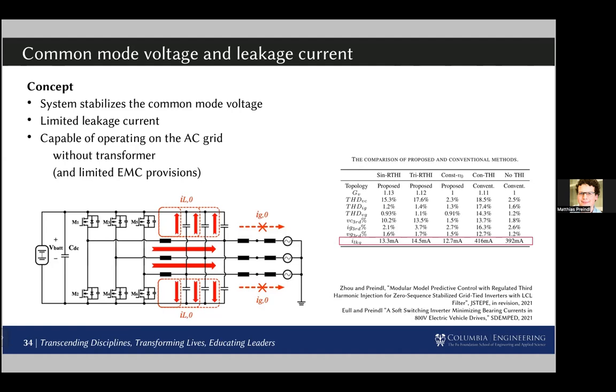What it means to have a stabilized zero or common mode voltage is, you can see at the right-hand side there is a table with the leakage current for a non-isolated inverter. With this system we are below 15 milliamp, which is typically a limit required by grid standards. If we don't stabilize the common mode, then we have the common mode voltage jumping up and down by half of the DC voltage.